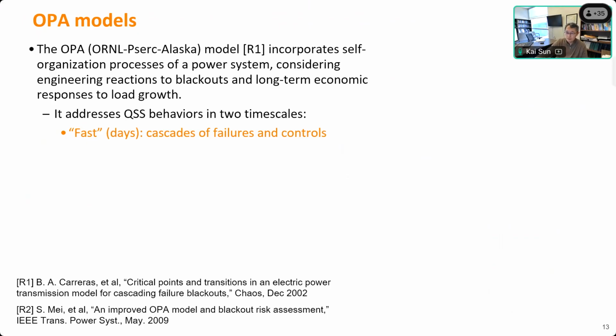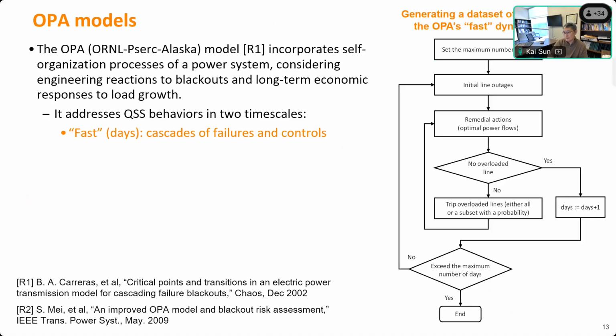So each day there will be a cascading event, and you can simulate many days to create a data set of events. If your system has a lot of cascades, you're going to upgrade the system. This flow chart indicates the basic idea of how to utilize the fast dynamic module of the OPA model to create a data set of cascading failure.